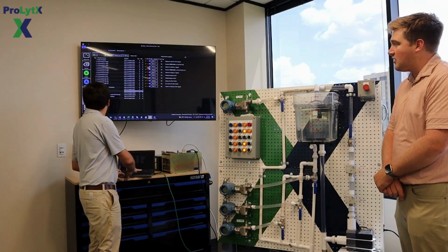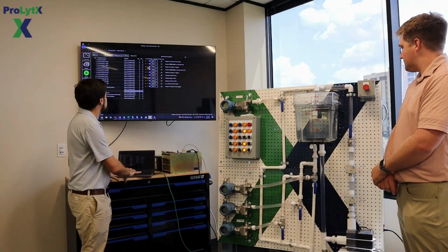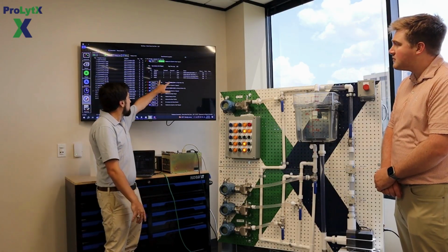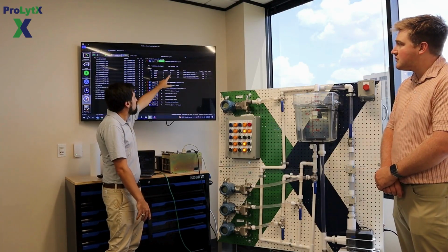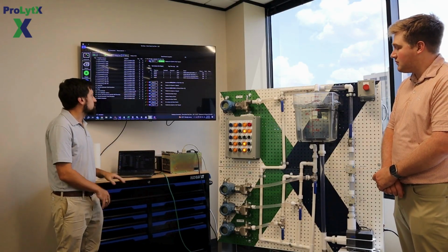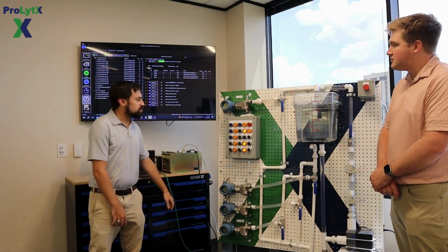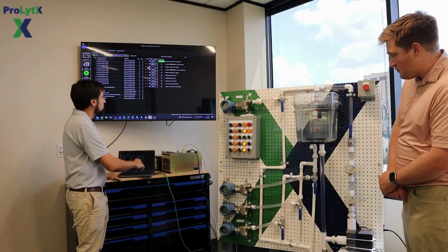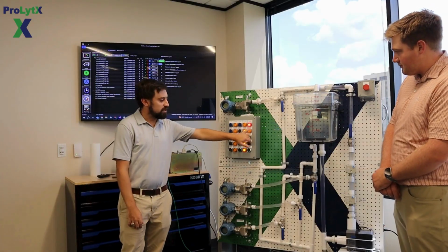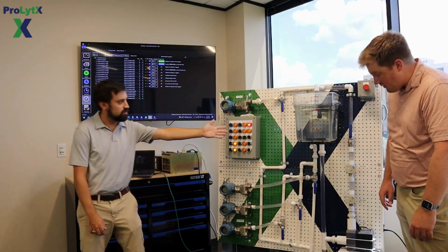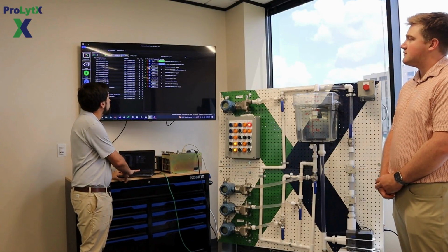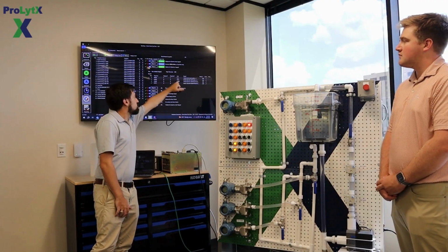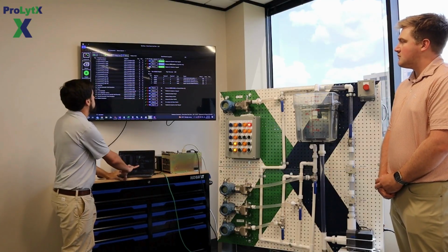Yeah, so right here I'll walk you through a shutdown on an ESD. First thing we're going to do is validate the system's not tripped. And how do we do that? We hit that button, but it's actually verifying that both valves and the motor are true right now, so it's not tripped, and that the trip light is off. So what we're going to do next is go ahead and trip it. We should see that trip light come on and everything shut down. We trip it, trip light's on, both valves are closed, motor stopped, no water is circulating. We can also verify that through this test right here. We see that we have false on both valves and false on the motor, true on the light. So we passed that step 2.